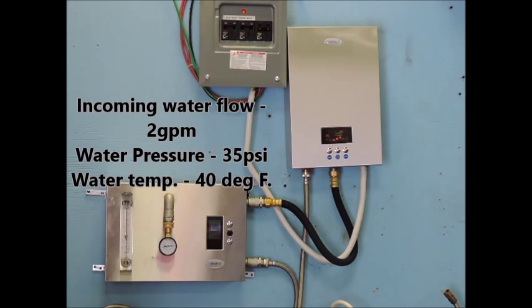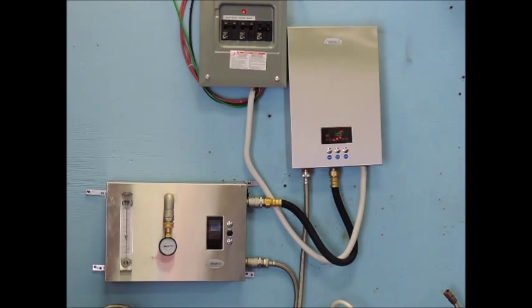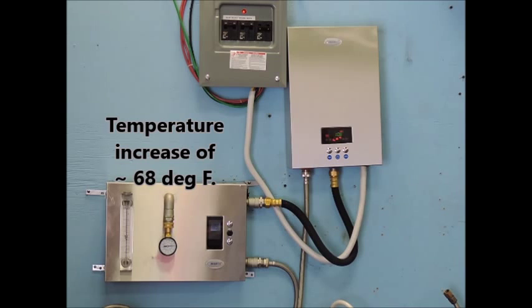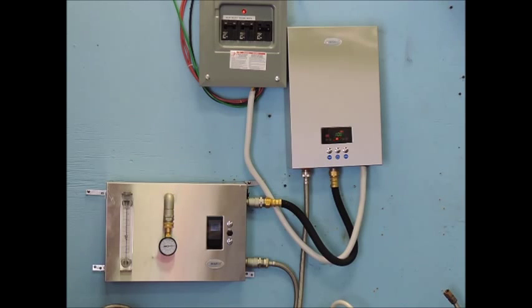Here we bring our flow down to 2 gallons a minute, still with 35 psi and 40 degrees incoming water temperature. As you can see in the drop of flow, we have an increase in temperature of 108, giving you a 68 degree rise.